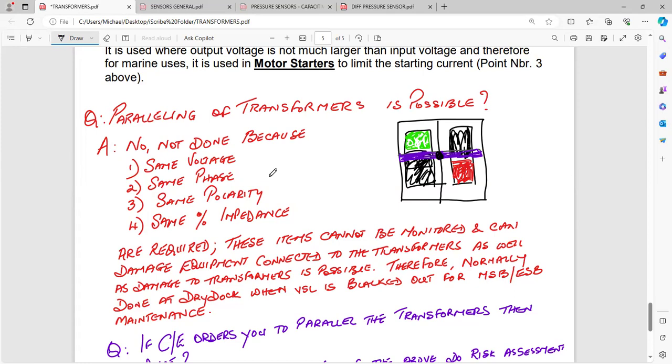And this is going to your two transformers over here, no? Transformer 1 and transformer number 2 for domestic purposes. So 440 volts is being given to either this transformer or this transformer for your domestic purposes. So either one of these two transformers is in action. So can these transformers be paralleled? When you're talking about paralleling, it means both being on together.